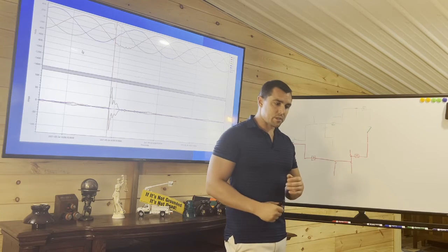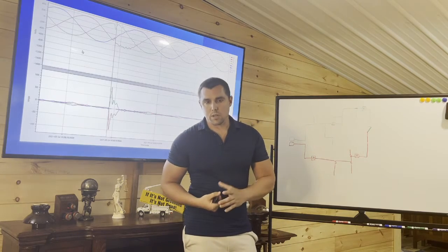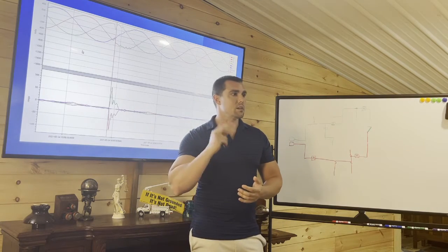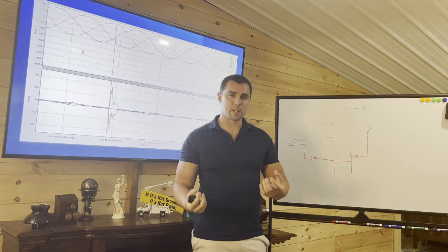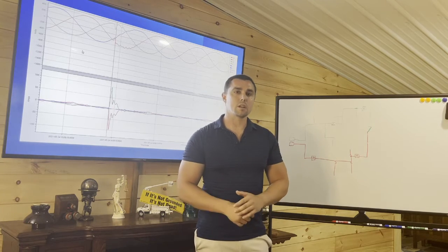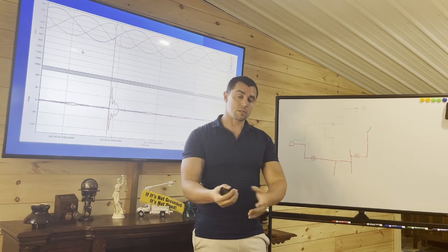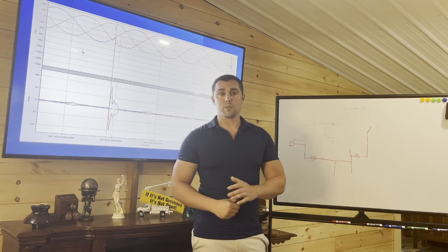customers down south, you look at Florida, we've seen a thousand times where a line would fall in an orange grove or something where it's very sandy. Line will just sit there because there's not enough available fault current, distance to the substation, distance to source, to actually blow the fuse.